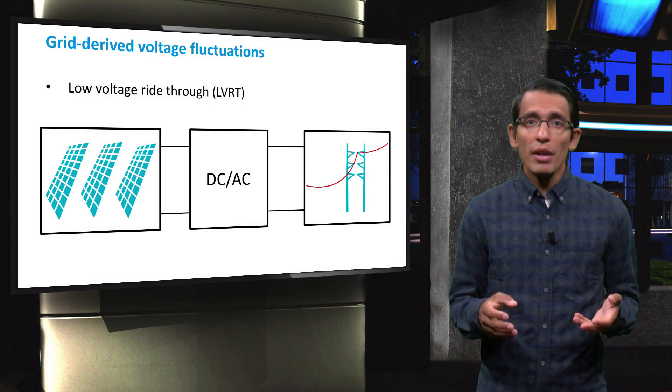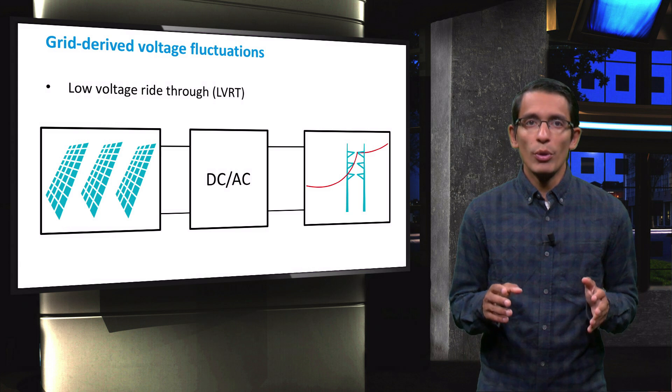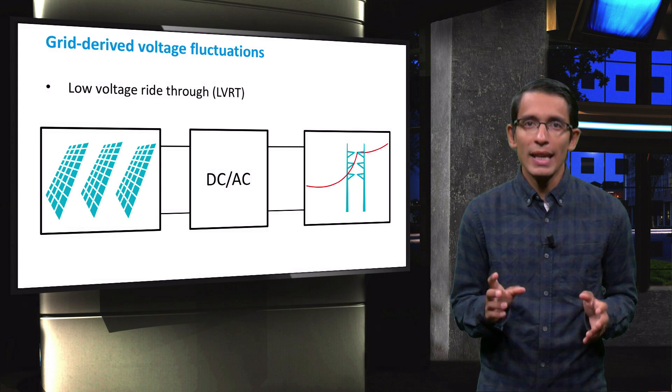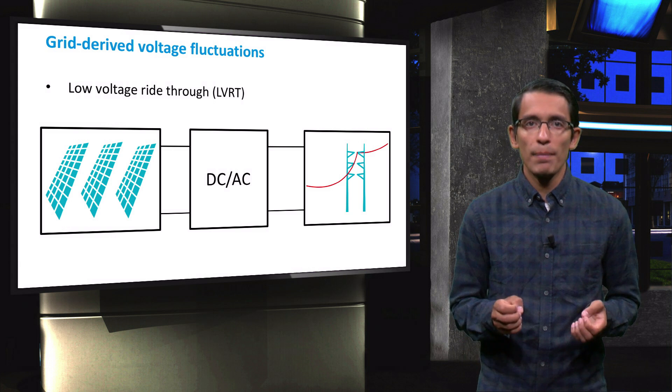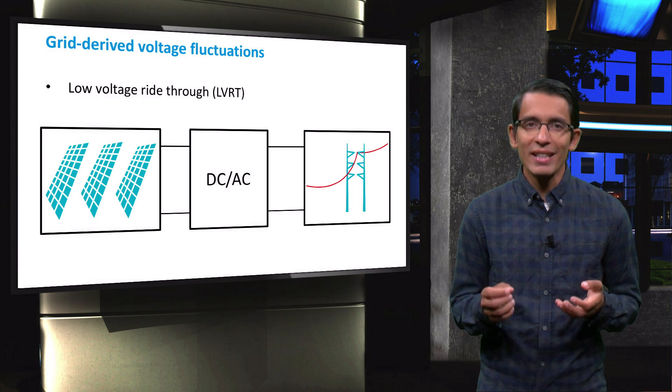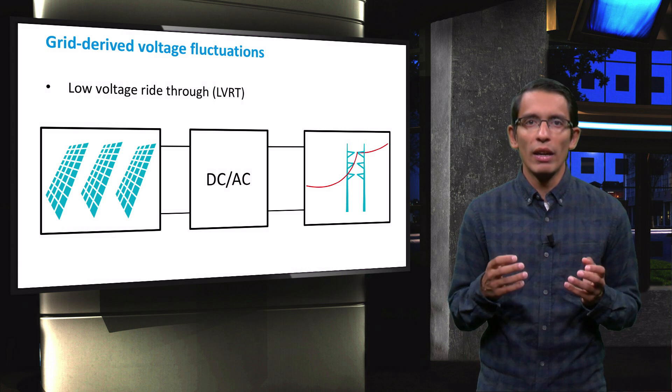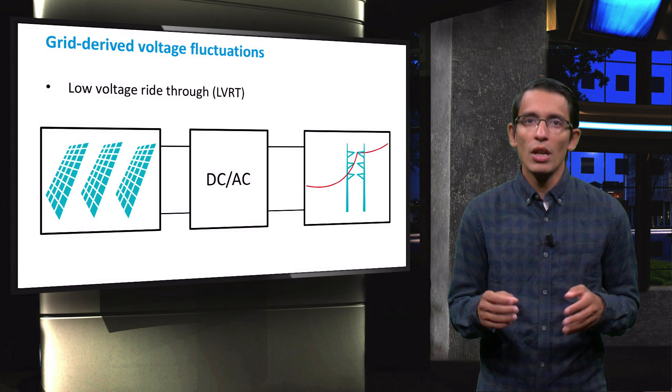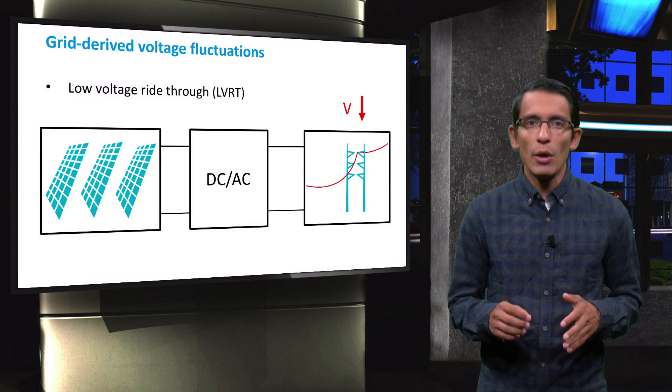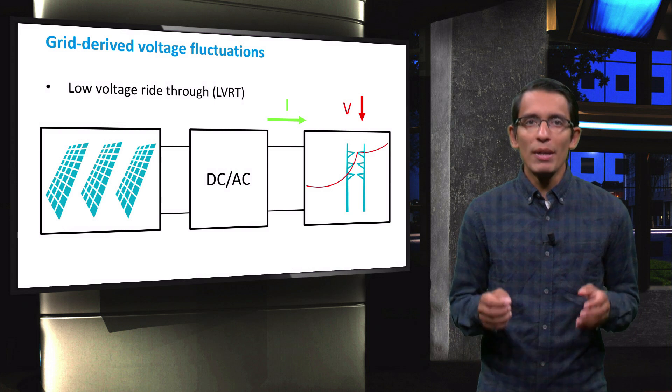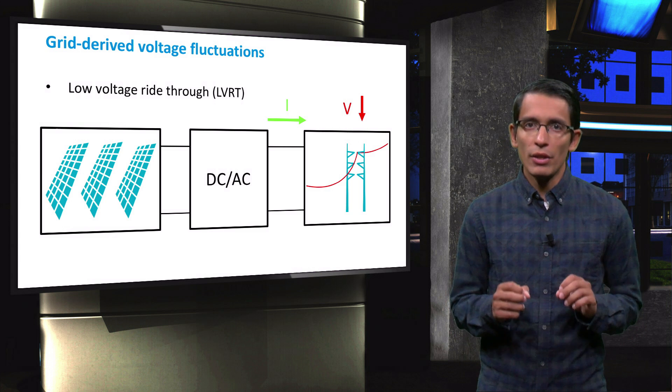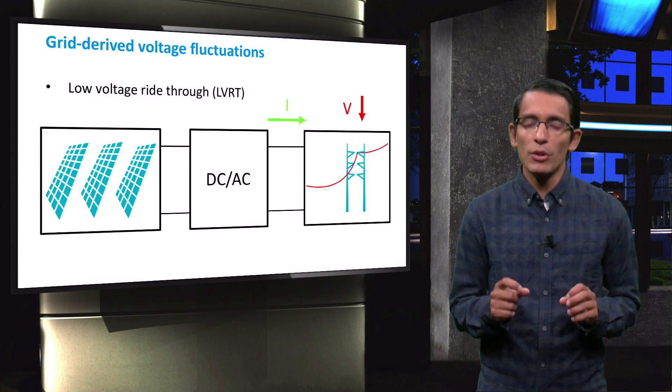One way to broaden voltage dip tolerances is to incorporate low voltage ride-through techniques into the inverter design. This term refers to the capability of electric generators to stay connected in short periods of lower electric network voltage or voltage dip. When the voltage of the distribution system goes down, the inverter is programmed to keep injecting current into the system. This way, the PV is able to remain connected to the grid for short period voltage dips or brownouts.